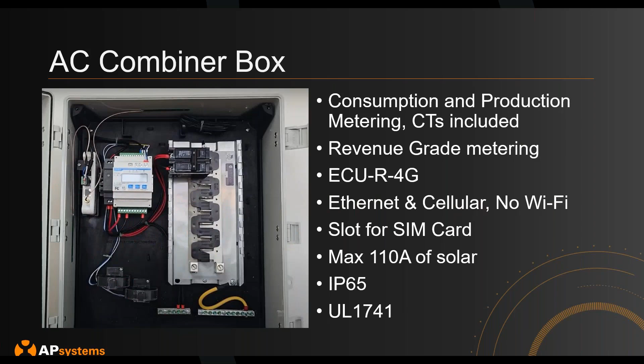Here's another view of the AC combiner box from a technical wiring perspective. Be careful that the phases are connected correctly. A common mistake that often happens is that when routing the strings, you want to put all the red wires into one CT and all the black wires into the other CT, which is generally good practice. Just make sure the red wires go into the right phase.